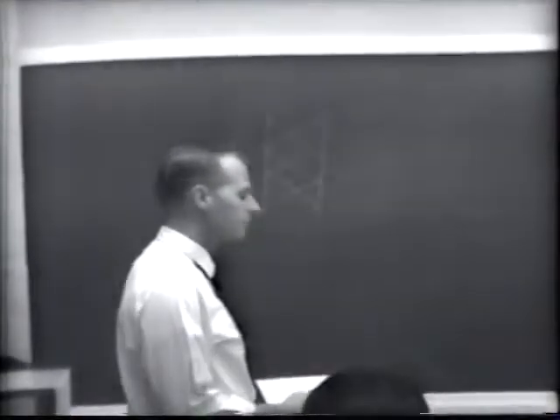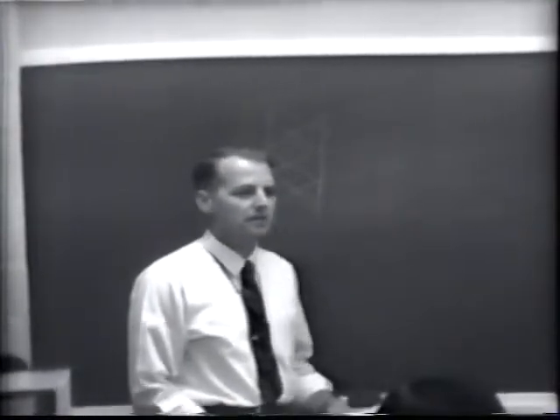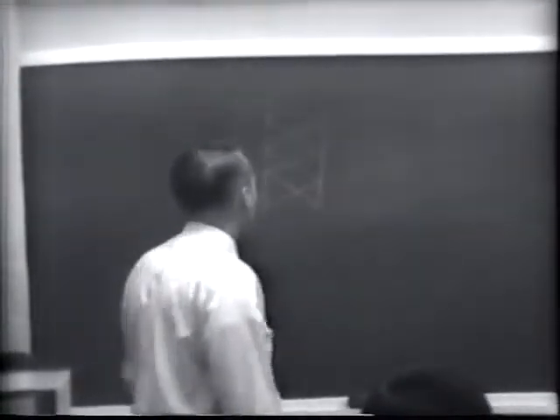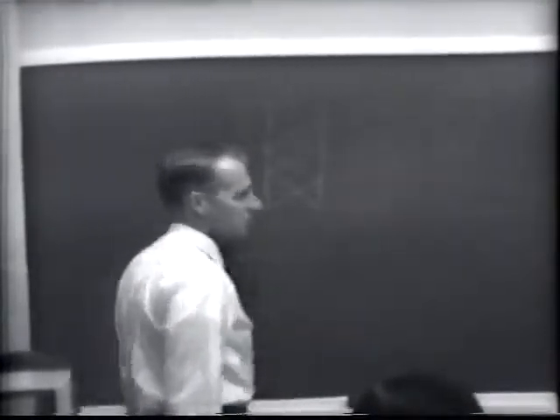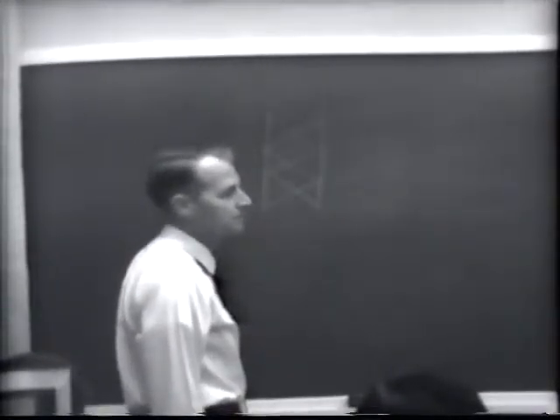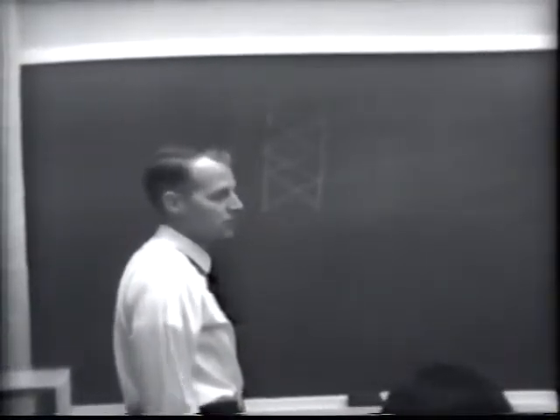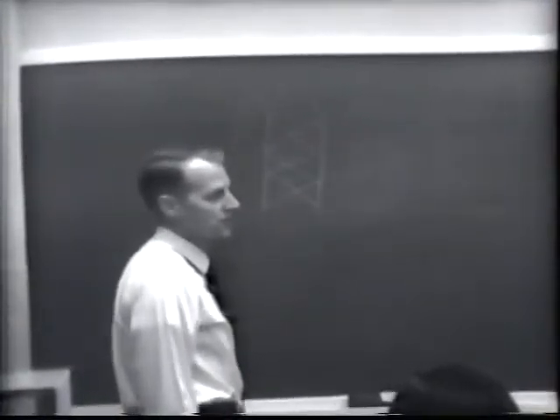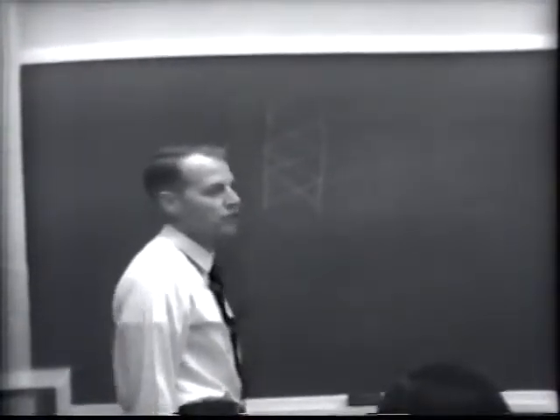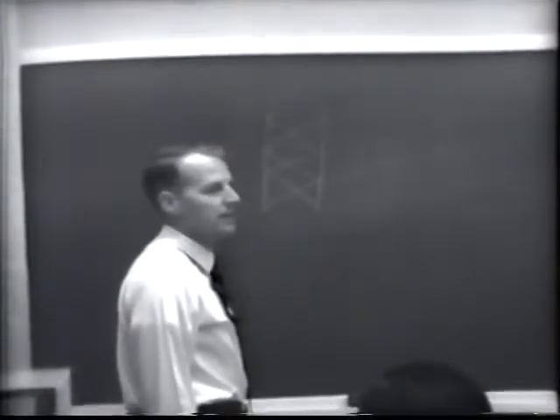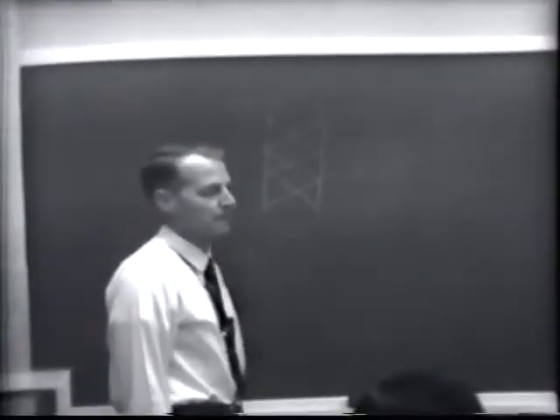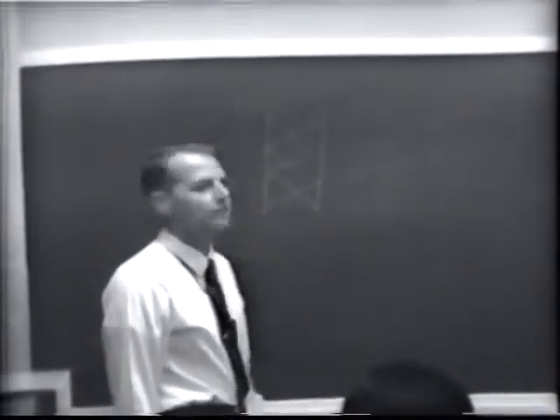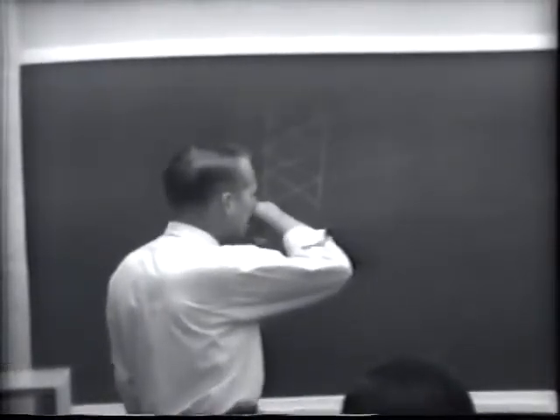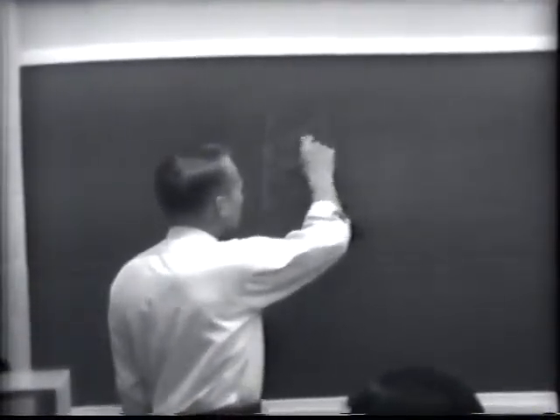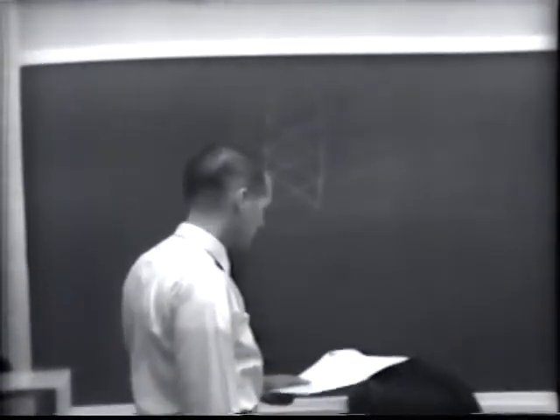Now, at the 161 kV levels and above, we're kind of forced to go into this type of structure because we're talking about separate structures. At the higher voltage levels, we don't have any continuous structure. We have separate structures for line dead ending, separate structures for disconnect switch mounting. So it's more economical of steel to go to a laced type construction like this.